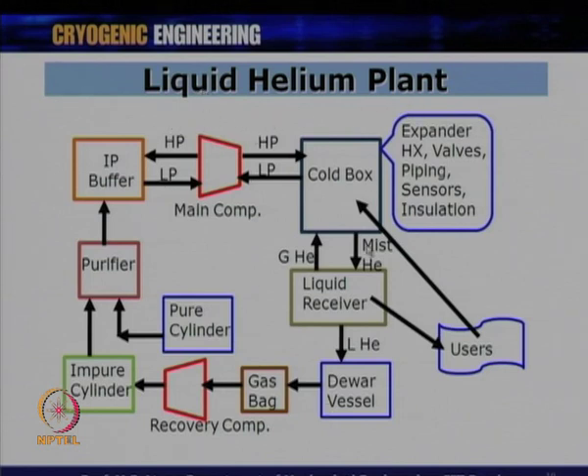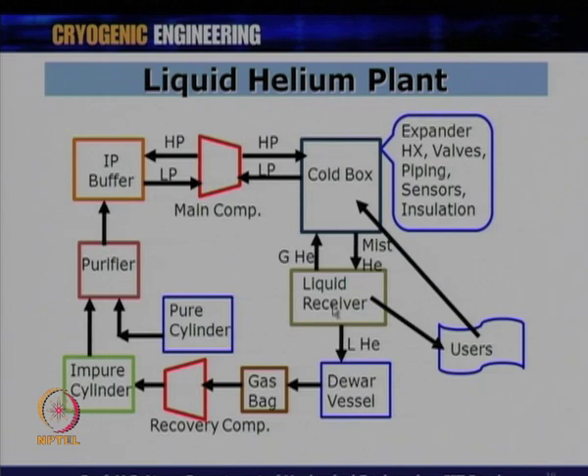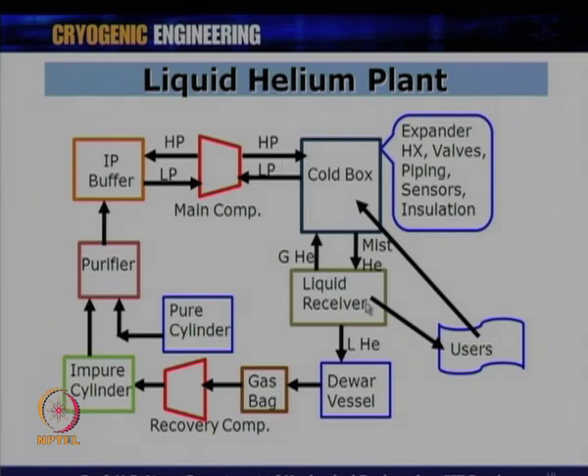The liquid helium plant schematic shows a cold box which houses expanders, heat exchangers, piping, sensors, and insulation. High-pressure gas from the compressor enters the cold box, liquid is produced and goes to the liquid receiver, while the remaining gas returns at low pressure continuing the cycle. The liquid helium produced is used directly by users at the site, or transferred to dewar vessels taken to different laboratories.